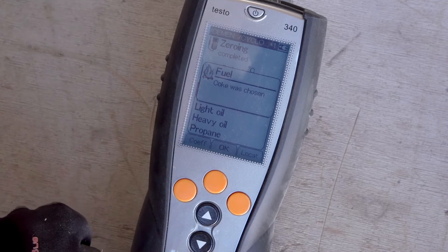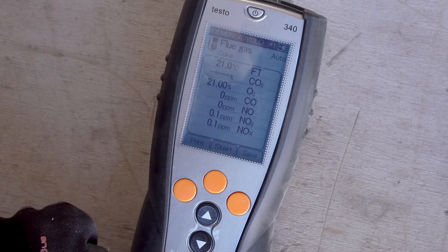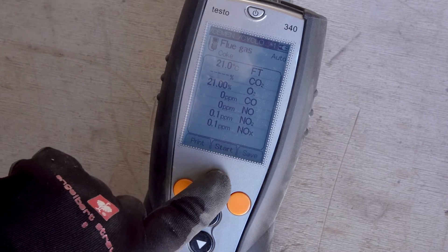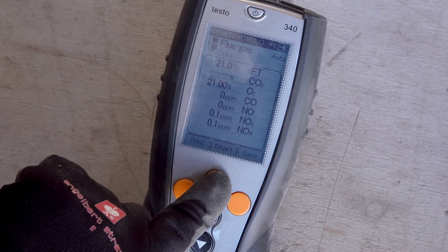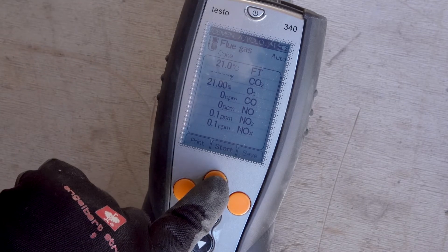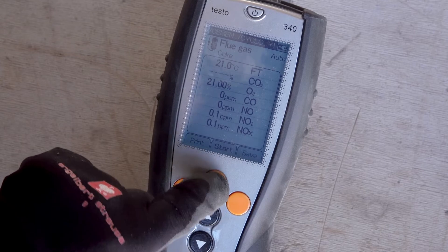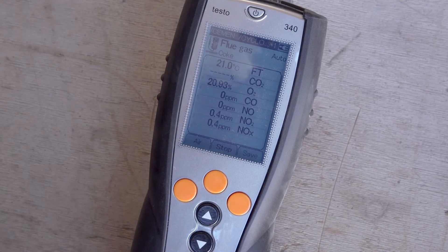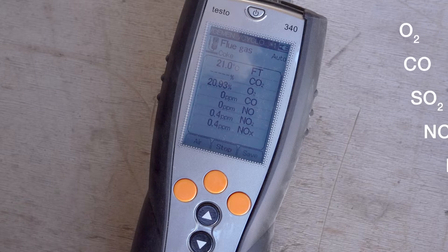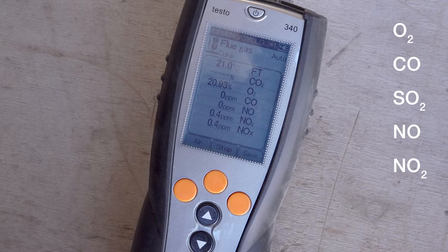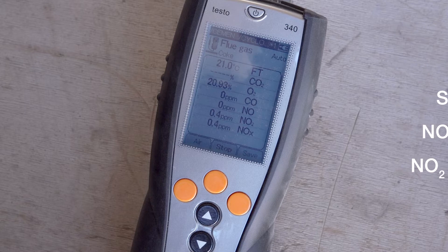After that, the zeroing phase of 30 seconds starts in the background. Then simply select the desired fuel — the probe tip should be in the center of the flue. The measurement is started via the menu item Start. The Testo 340 can be equipped with up to four sensors for measuring oxygen, carbon monoxide, sulfur dioxide, nitrogen monoxide, and nitrogen dioxide.